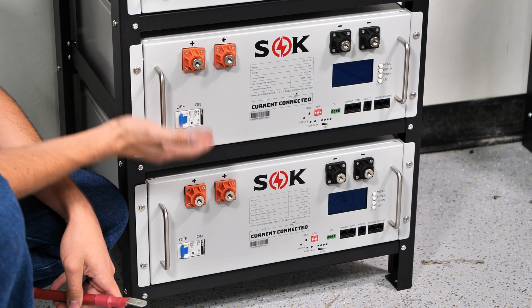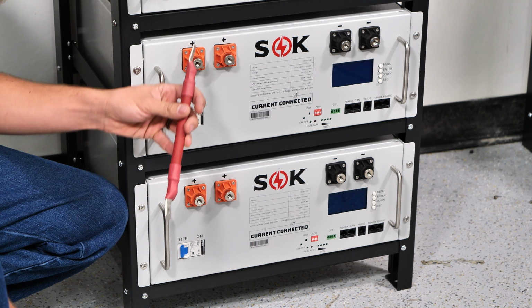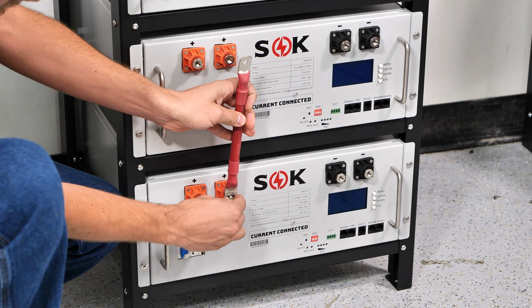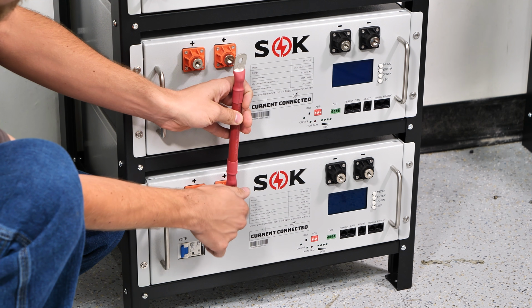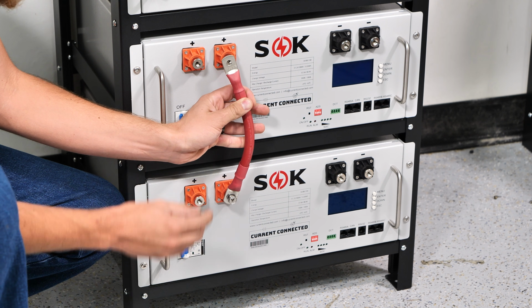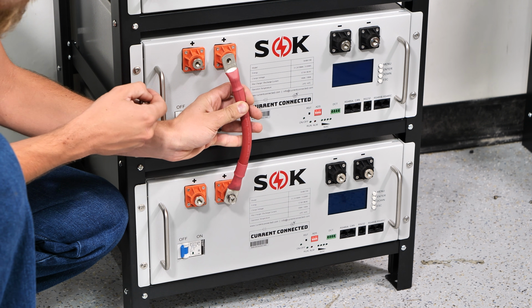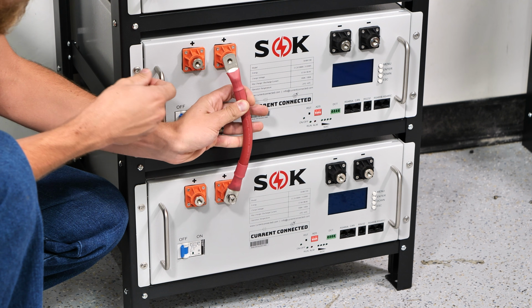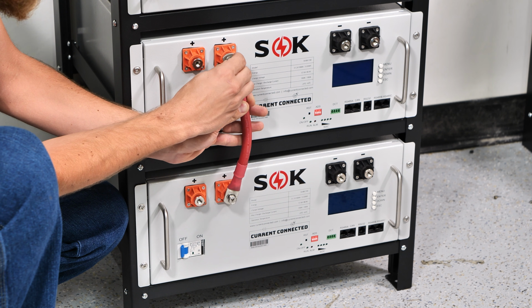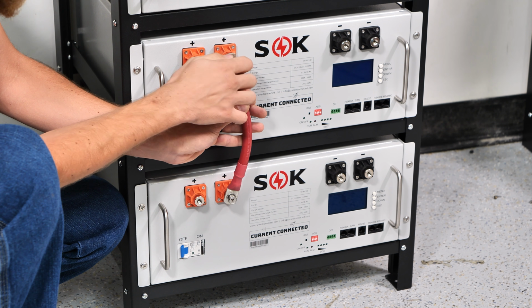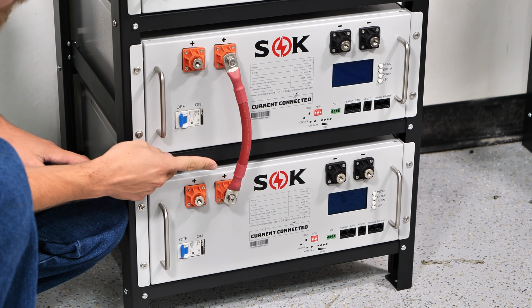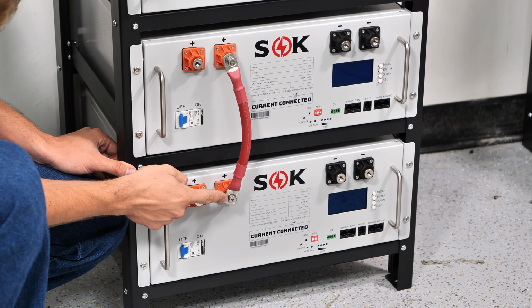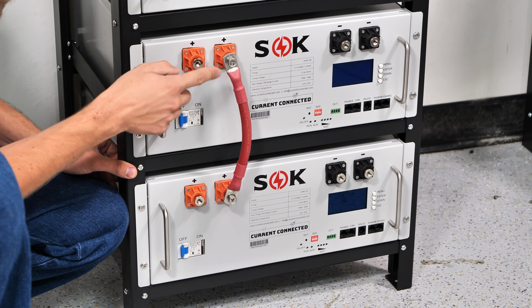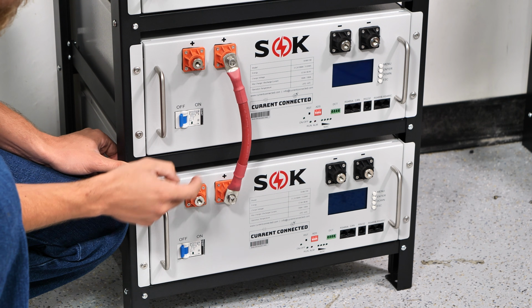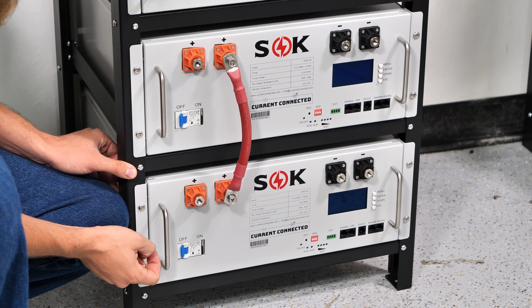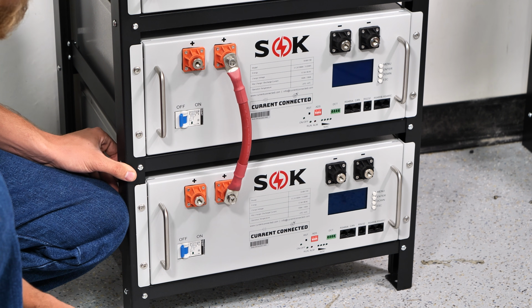I like starting from the bottom up, so here we are at the bottom of the rack. First thing I'm going to put in is my red wire here. So I'm going to get the screws all started hand tight, and then in the end I'll come back and torque them. Now, something that's really nice about this 9-inch length is it gives us a little bit of extra wiggle room. So if we bend them in the middle a little bit, they fit perfect. But the reason I wouldn't want this to be the exact length from center to center is because if we have any deviation or tolerance here, it's just not going to fit. So that's why 9 inches is the perfect length.